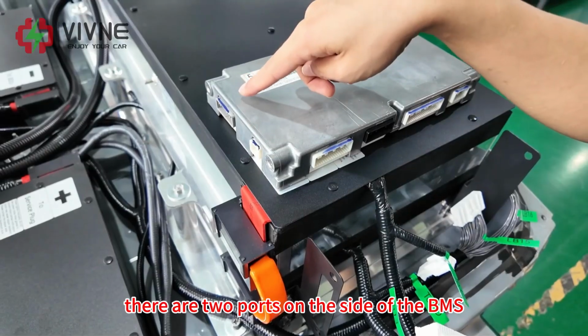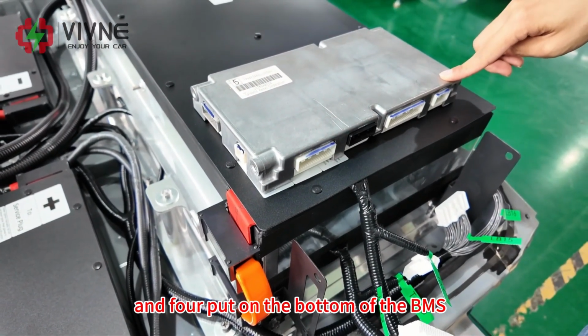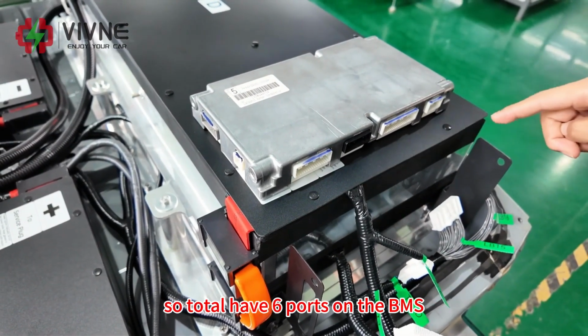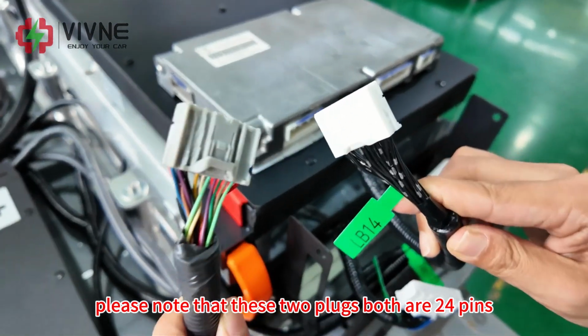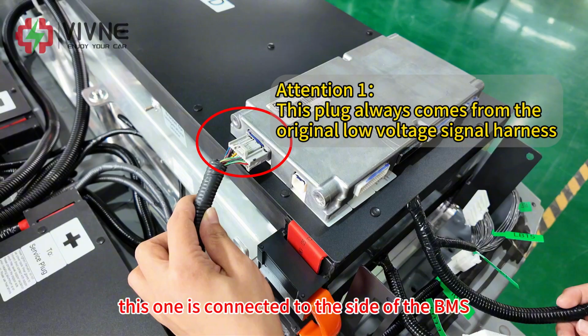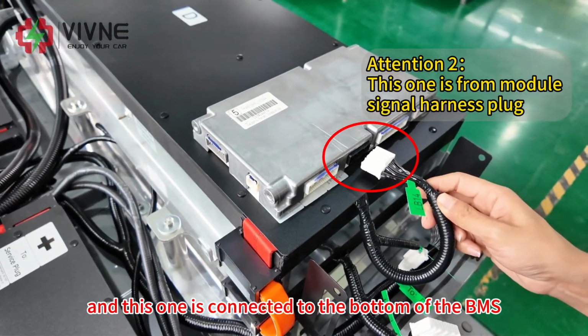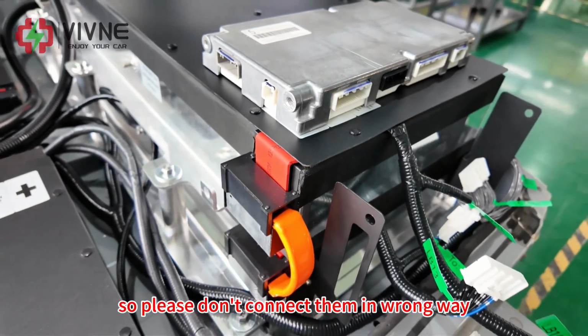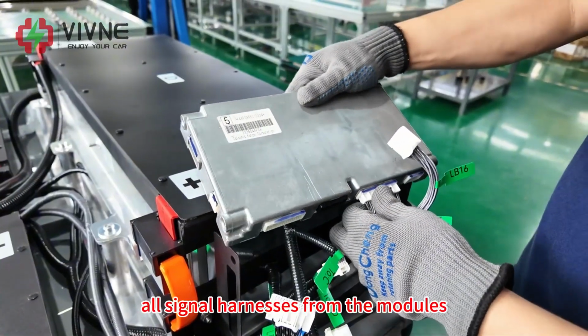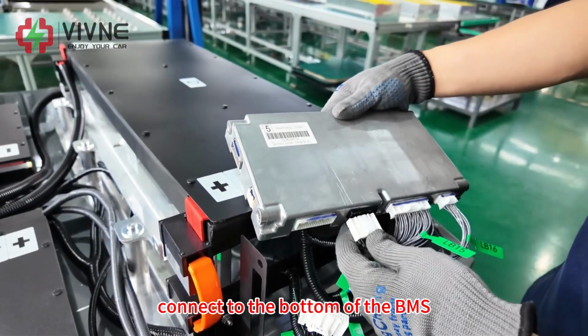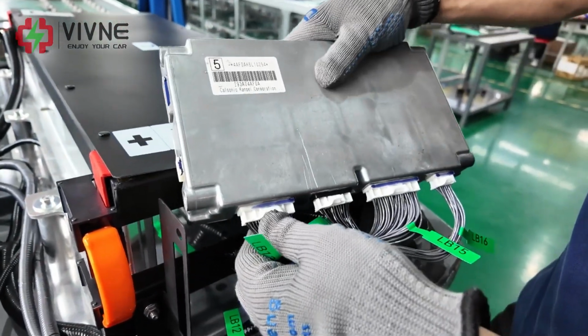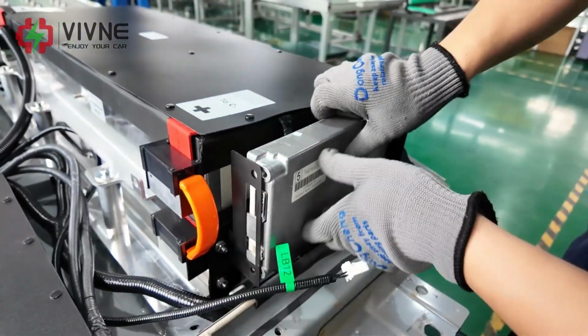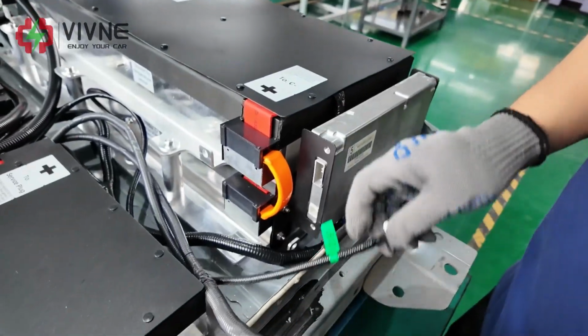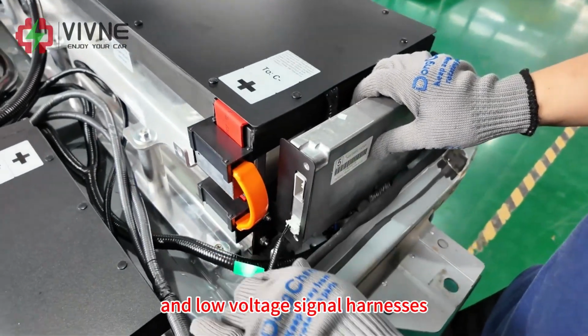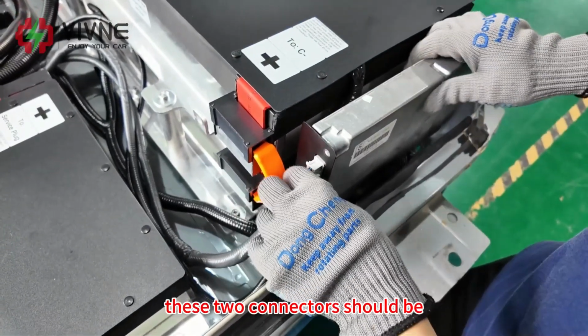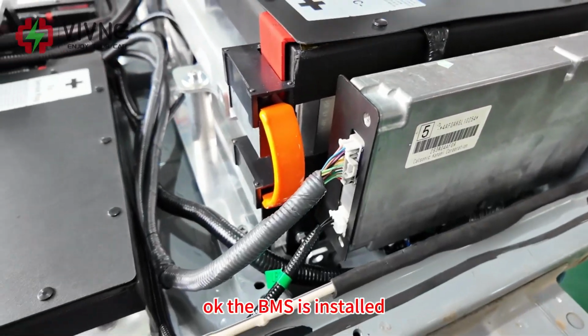There are 2 ports on the side of the BMS and 4 ports on the bottom of the BMS, so in total there are 6 ports on the BMS. Please note that these 2 plugs are both 24 pins. This one is connected to the side of the BMS, and this one is connected to the bottom of the BMS. So please don't connect them the wrong way. Please remember a simple rule: all signal harnesses from the modules connect to the bottom of the BMS. This plug is for temperature sensors and has no voltage signal harness. These 2 connectors should be connected to the side of the BMS. Okay, the BMS is installed.